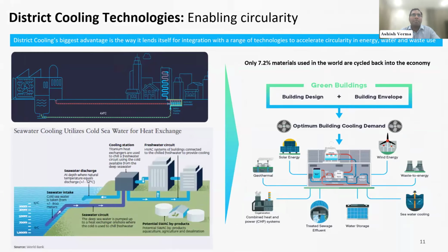District cooling can also help us in enabling circularity, which is a very important subject nowadays, because we have to have circularity in our resources. The statistics are that only 7% of material in the world is being recycled, and this is something we have to focus upon. District cooling is a very good medium where we can integrate all the technologies and recycle the components. There are multiple options for how we can do it, but before that, what's normally done is we first have to reduce the demand. We can always install 20,000 tons, 30,000 tons, but we obviously have to optimize the demand.